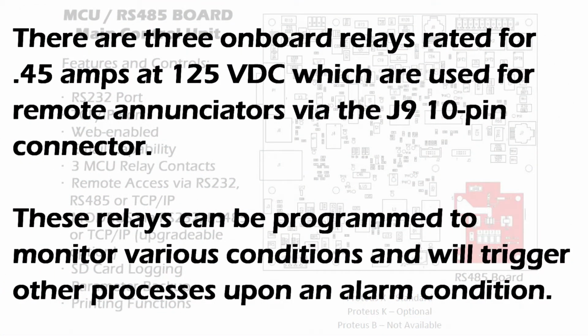There are 3 on-board relays rated for 0.45 amps at 125 volts DC, which are used for remote annunciators via the J9, 10-pin connector. These relays can be programmed to monitor various conditions and will trigger other processes upon an alarm condition.